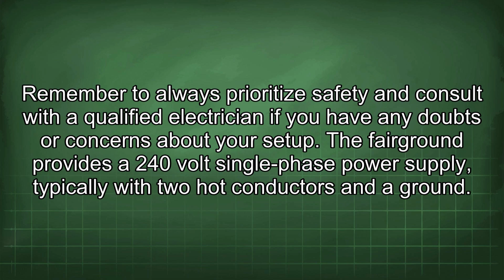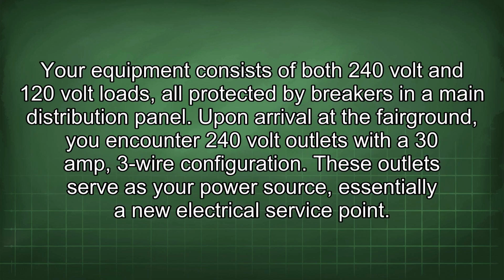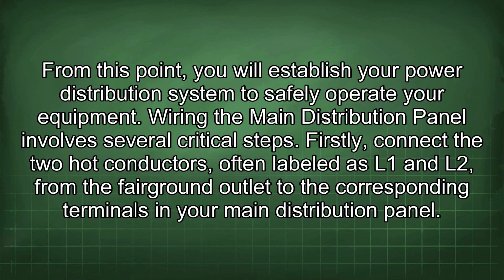your setup. The Fairground provides a 240-volt single-phase power supply, typically with 2 hot conductors and a ground. Your equipment consists of both 240-volt and 120-volt loads, all protected by breakers in the main distribution panel. Upon arrival at the Fairground, you encounter 240-volt outlets with a 30-amp, 3-wire configuration. These outlets serve as your power source, essentially a new electrical service point.